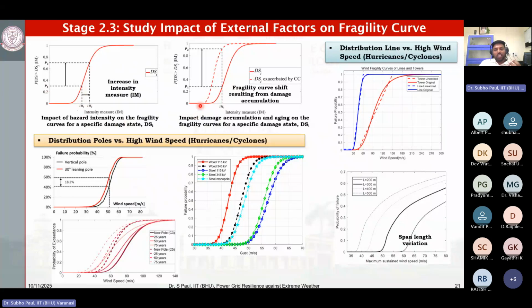If you see the image at the top row, middle one, this solid red line is the fragility curve for a particular equipment when it is brand new. But when it has been affected multiple times by damage, and damage accumulation has happened, after certain years this fragility curve can shift to the left. So for the same intensity level, the failure probability for the new one was quite low, but for the old one, when the accumulated damage has become very high, the failure probability also becomes very high.